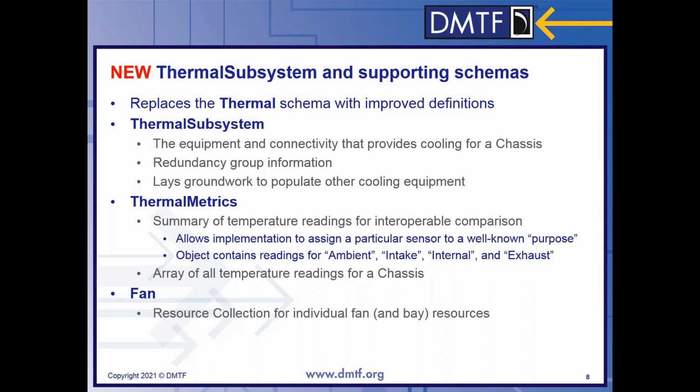Separately, and again, just like we had on the power supply metrics, there is a more global thermal metrics resource. As a start, we focused just on temperature readings, but within the thermal metrics, there are actually two structures. There's one that's a summary of temperature readings, and those have been given specific sensors with specific names, and obviously every implementation can map those values to the sensors that make sense for your implementation.